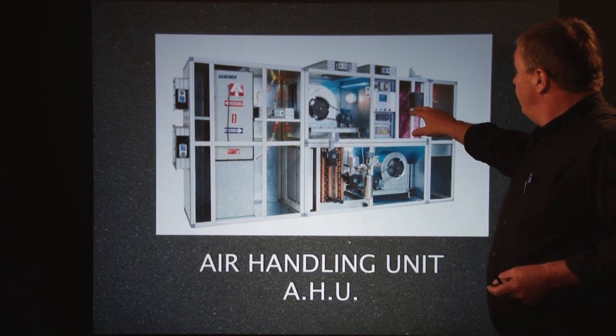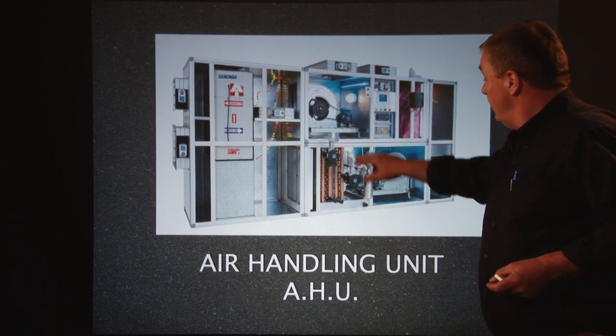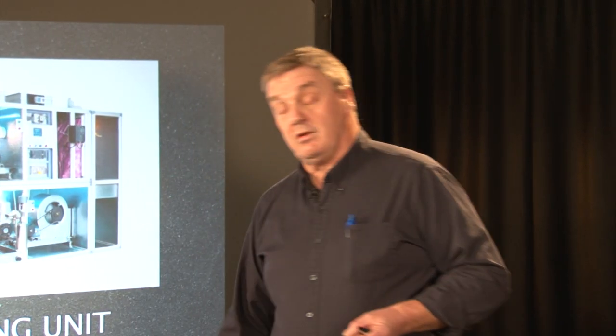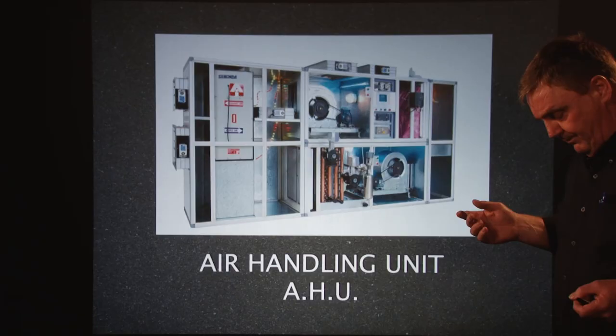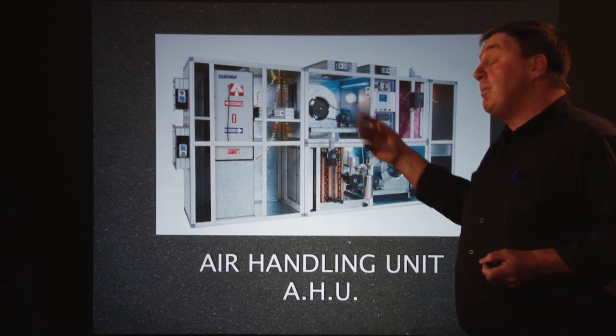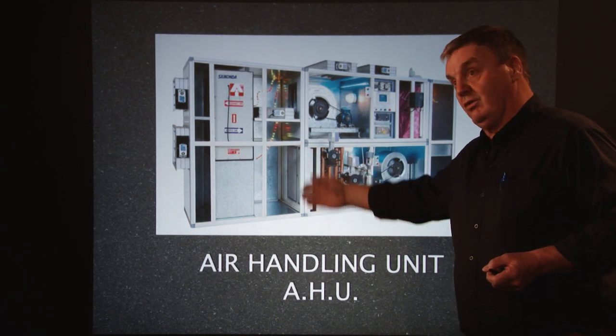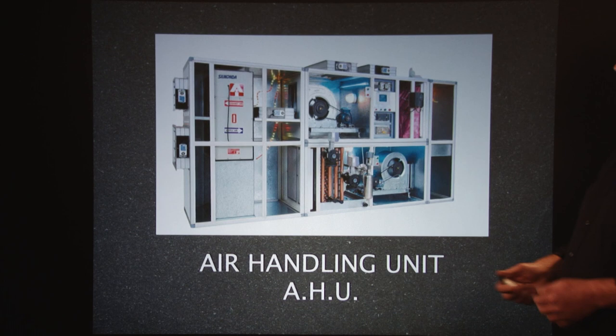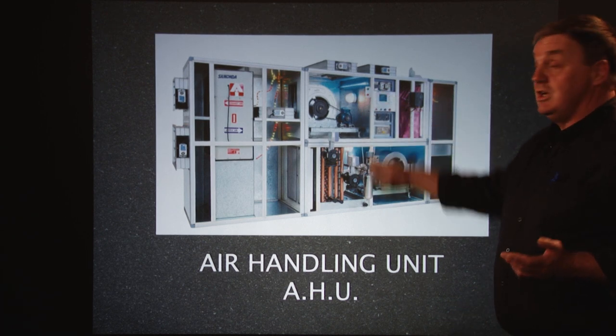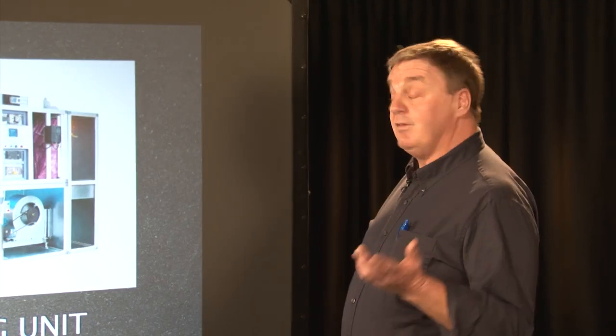You can see there's insulation in here and all the electrical controls. There are even lights in this one so that for maintenance they can come in, check belt tensions, and make sure the fans are working and going the right way around. If you have a third-party inspector, he'll know what to look for. If you decide to take a panel off, about the only one you'll really need to take off is to see if the filter's clean or has it been changed. You can write a report on what you see — any physical damage — but the expert would give you a more in-depth report.